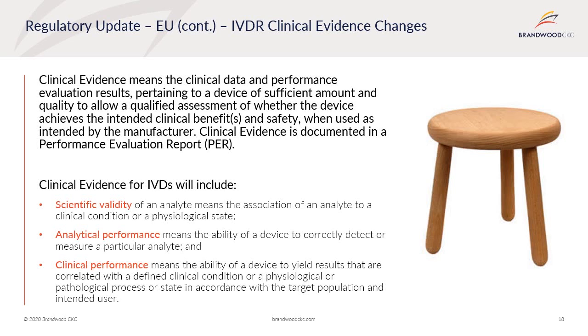Now, again, I will reiterate, because this is a question we get a lot, does this mean I need to do clinical studies? And the answer is maybe, but generally, especially if you've been marketing this product under the IVDD, you should have plenty of evidence from your real world and your post-market surveillance to be able to support your clinical performance and your overall product performance. So in most cases, it's just justifying that. In some cases, especially those where classifications have changed or that it hasn't been on the market that long or it is extremely novel and high risk, you may need to consider clinical studies.